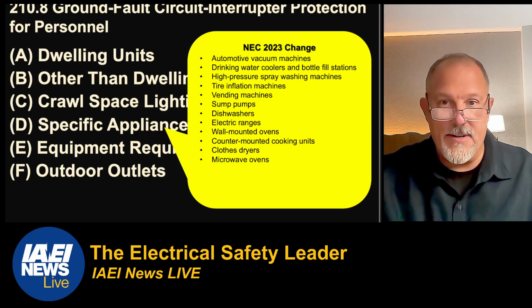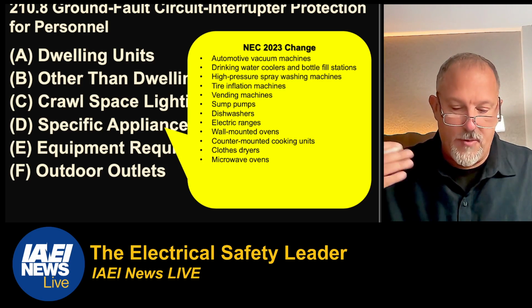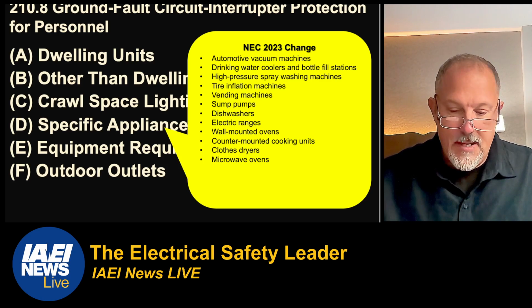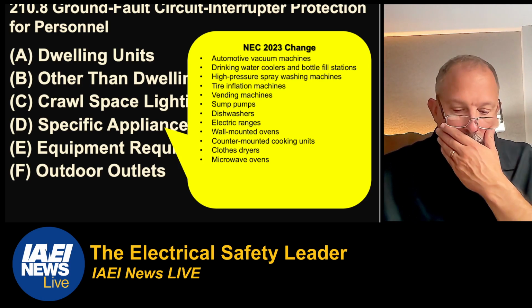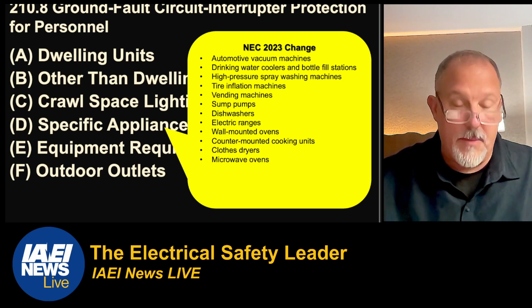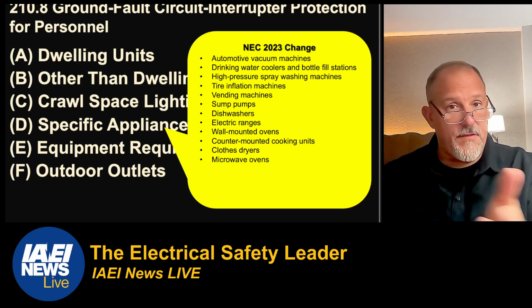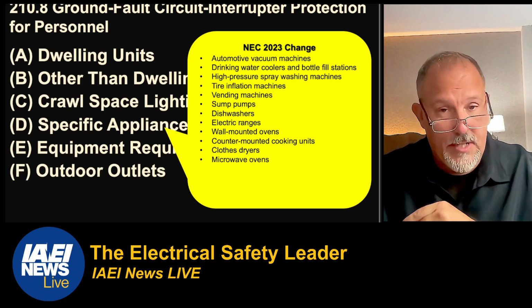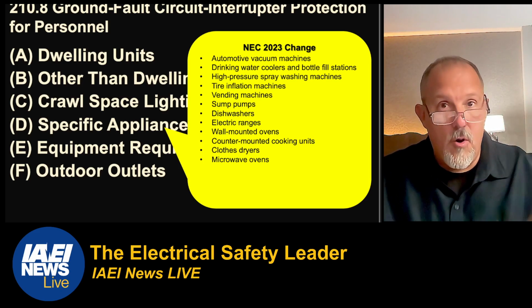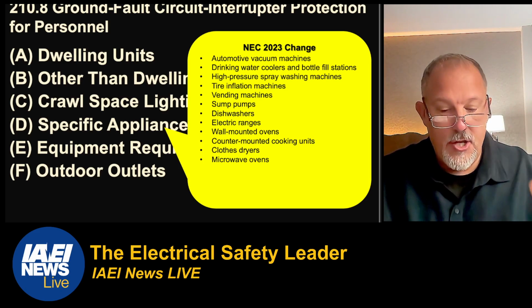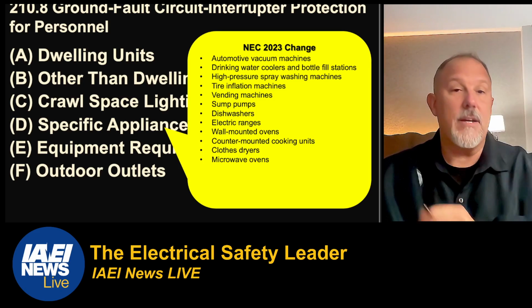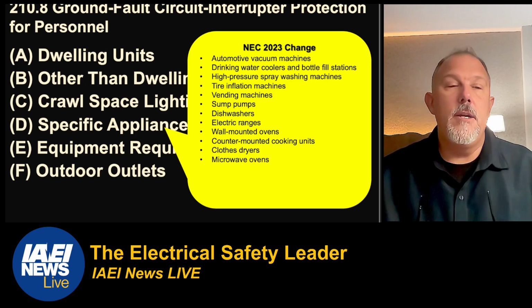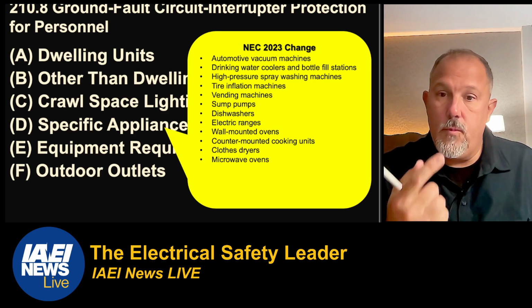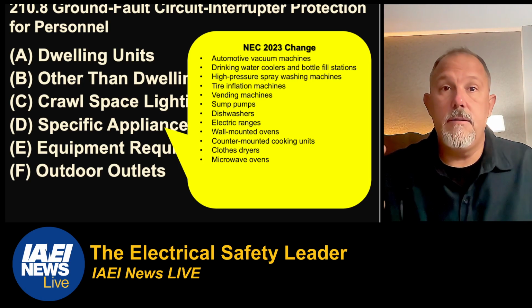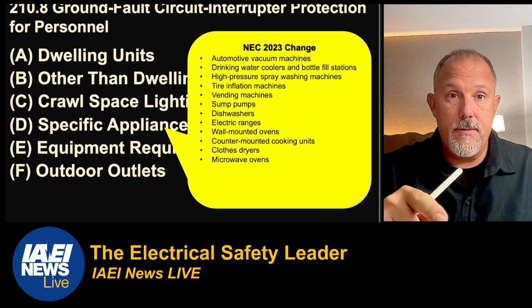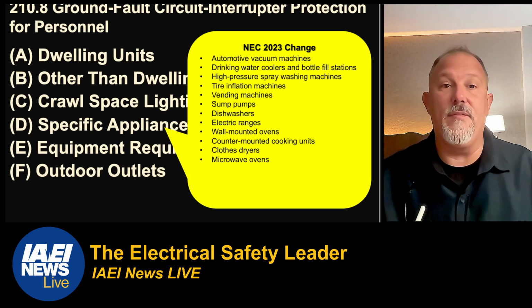So what you're seeing here is automotive vacuum machines, drinking water coolers and bottle fill stations, high pressure spray washing machines, tire inflation machines, vending machines, sump pumps, and dishwashers. Now, if you go back to Article 422, you're going to find that same list. What Panel 2 added was electric ranges, wall-mounted ovens, counter-mounted cooking units, clothes dryers, and microwave ovens. I'll give you a reason why. Two things. First, we had CPSC deaths on this equipment, on those wall-mounted ovens, microwave ovens, and clothes dryers.